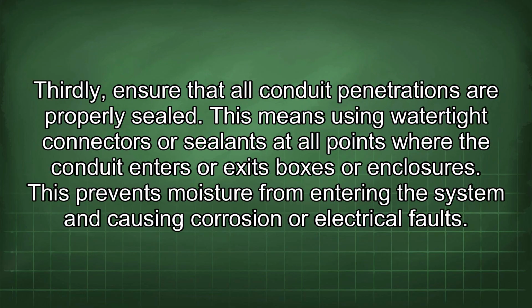Thirdly, ensure that all conduit penetrations are properly sealed. This means using watertight connectors or sealant at all points where the conduit enters or exits boxes or enclosures. This prevents moisture from entering the system and causing corrosion or electrical faults.